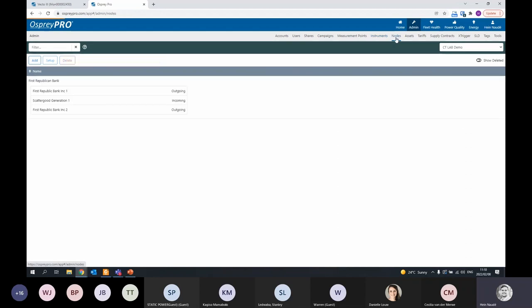Going on, you have settings. You can set up nodes and assets. A node, for example, is if you're measuring on the incomer of a substation and then 2 feeders or 2 load centers, you can create a node, and on that node you can generate different reports. For example, if you want to calculate the technical losses of a transformer, you can create a node for the incomer of the transformer and the output of the transformer if you're measuring on both sides, and generate a report that provides the technical losses over that transformer. So there's quite a lot you can do with that.